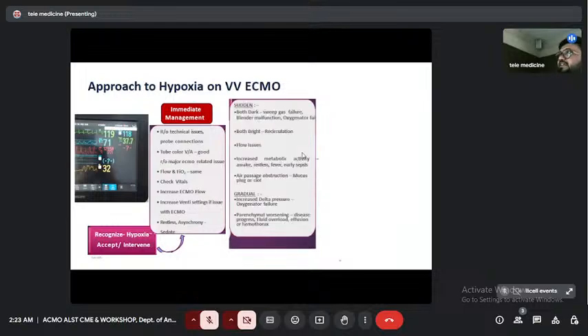if sudden hypoxia is there and both drainage and return cannulas are dark color, that may be because of a sweep gas failure, blender valve malfunction, or oxygenator failure. If both are bright, that means recirculation, because this is a VV ECMO. And flow issues, we have to correct that one.